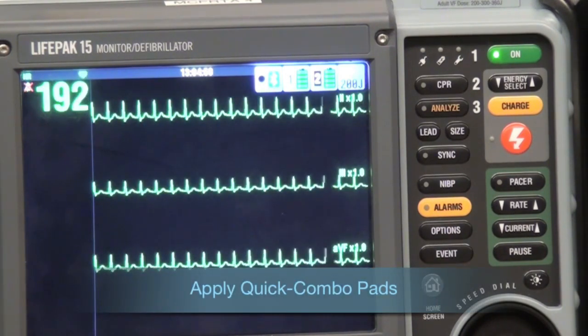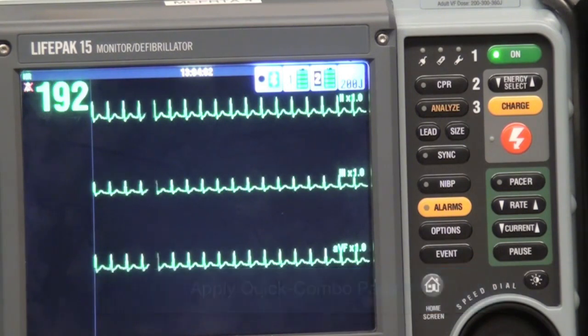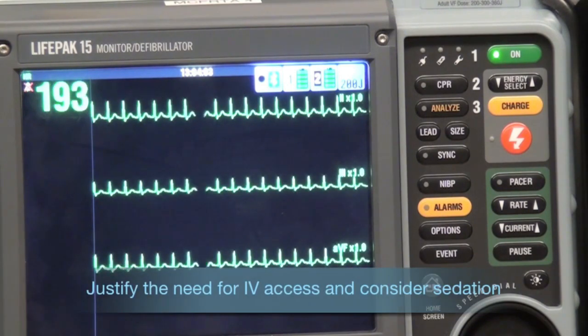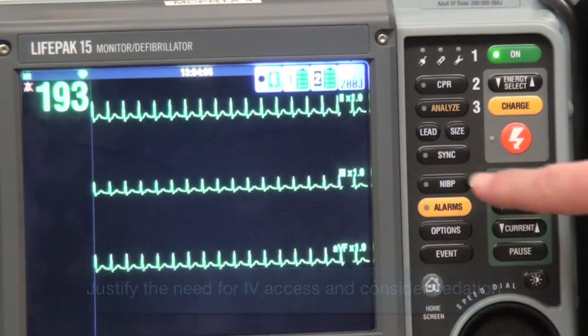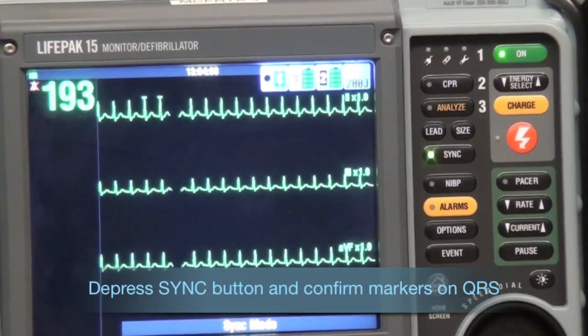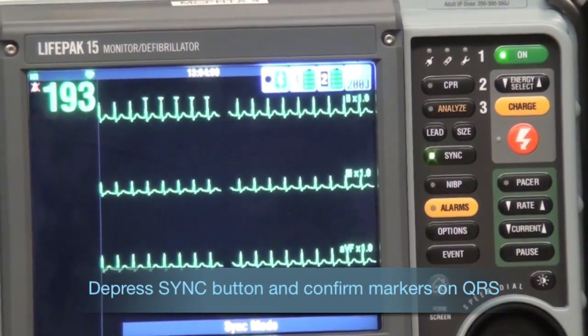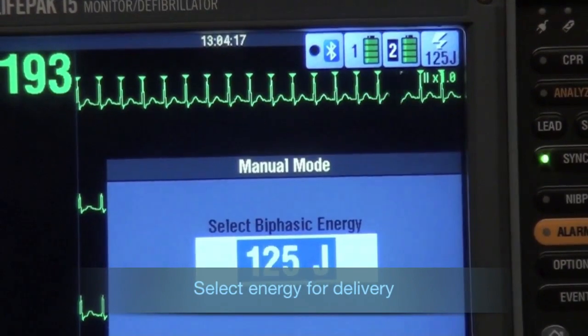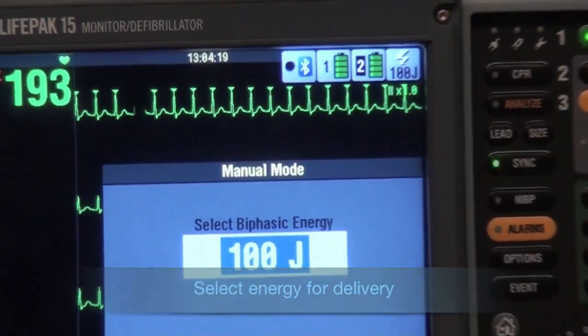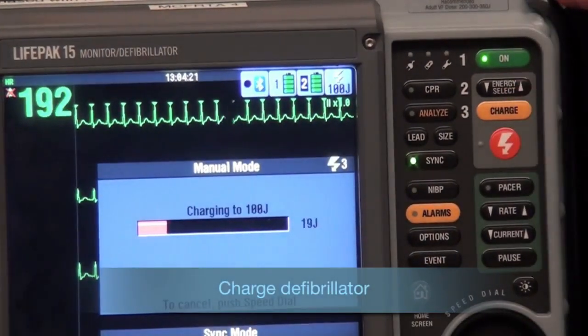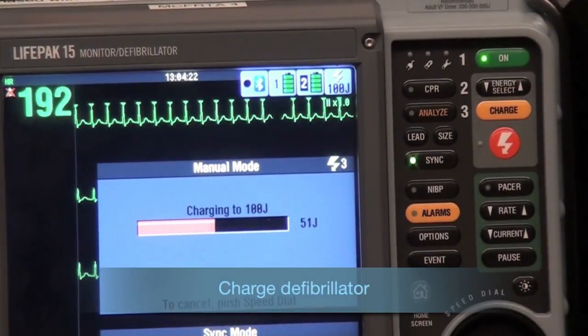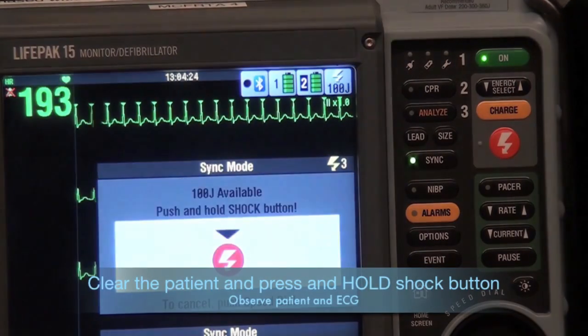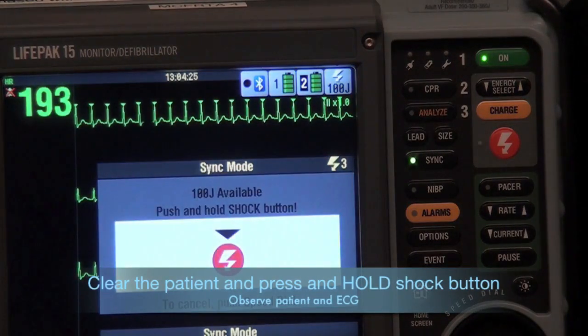When the sync option is engaged on a defibrillator and the shock button pushed, there will be a delay in the shock. During this delay the machine reads and synchronizes with the patient's ECG rhythm. This occurs so that the shock can be delivered with or just after the peak of the R wave in the patient's QRS complex.